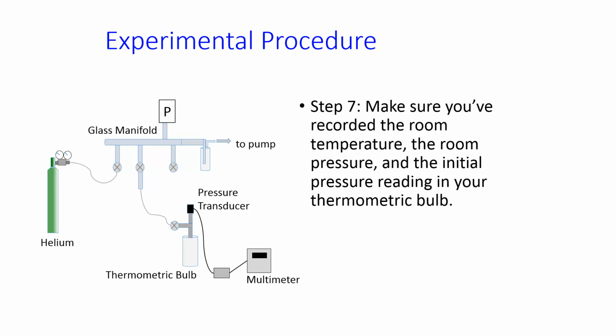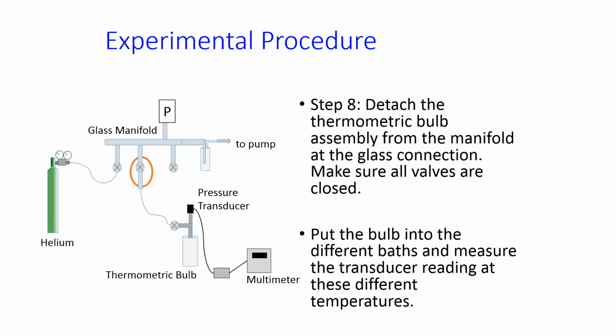At this point, you should remember to record the room temperature, the pressure in the room, and the initial pressure reading in your thermometric bulb, which is the same as the pressure in the manifold at this point. After you've done that, close all the valves and detach the thermometric bulb from the manifold at the connection that's shown here. You're going to move the bulb and physically put it into the different phase transition baths. So you're going to submerge it in ice water or in a steam bath or whatever. And you're going to record the multimeter voltage or your MATLAB voltage at these different temperatures.